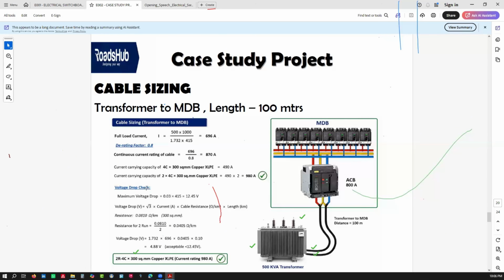But when you do a voltage drop check, you find it has 4.88 volts, which is less than 12.45, the maximum voltage drop level we need, just 3% of 415. If that value is below this, it means the cable is correctly selected for that job. So we have 2 runs of 4-core 300 squared mm copper XLPE rated at 980, since it's twice 490.